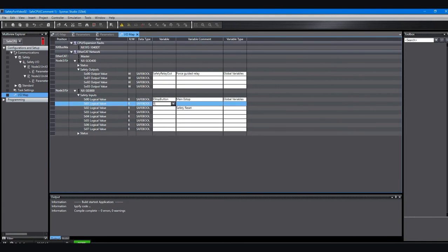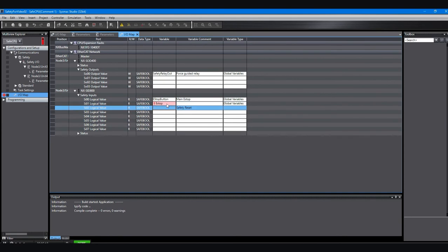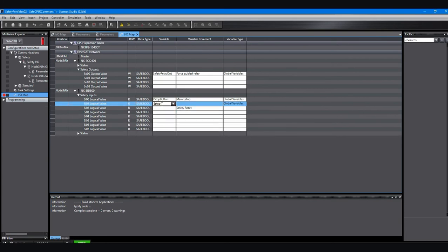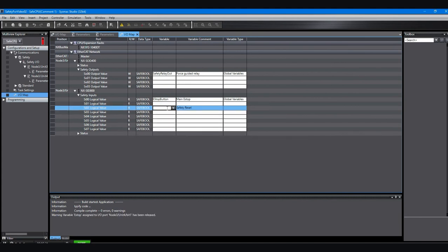Notice what happens if I try to put a name in on the second input, because both of those are used by that same e-stop switch. And it knows that, the PLC software knows that. So it'll give me an error. So I have to delete that variable name. And I'll go down here to put in the one for the reset.